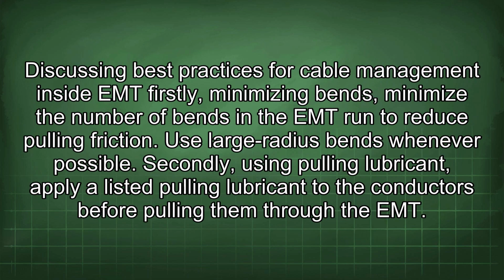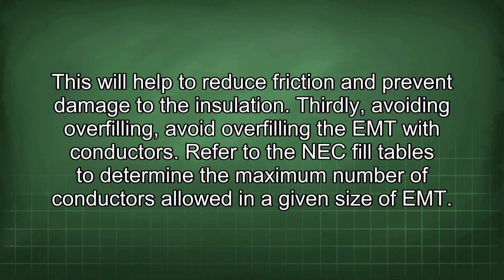Discussing best practices for cable management inside EMT. Firstly, minimizing bends. Minimize the number of bends in the EMT run to reduce pulling friction. Use large radius bends whenever possible. Secondly, using pulling lubricant. Apply a listed pulling lubricant to the conductors before pulling them through the EMT. This will help to reduce friction and prevent damage to the insulation.